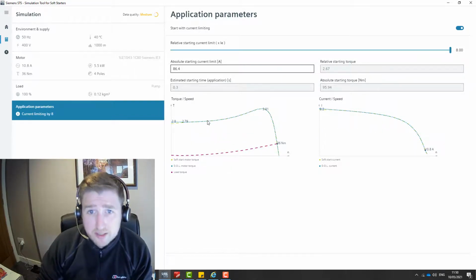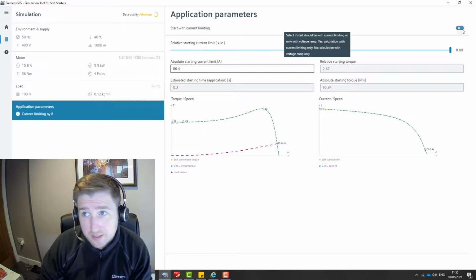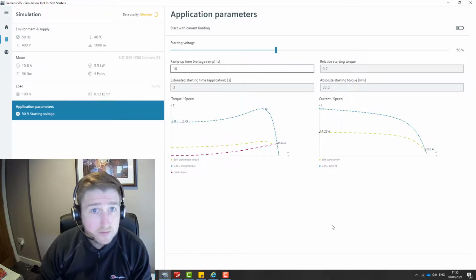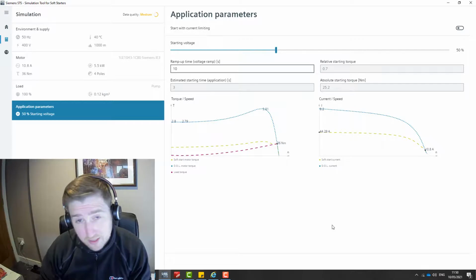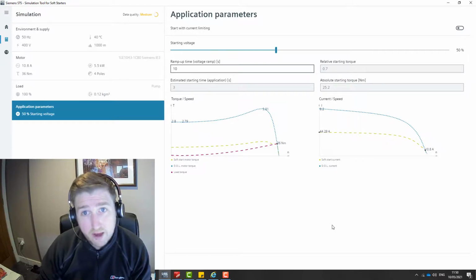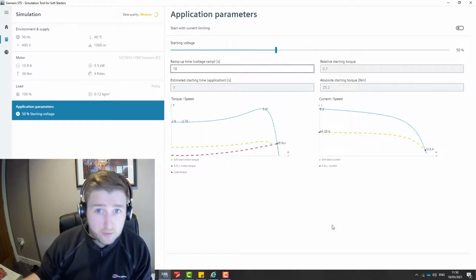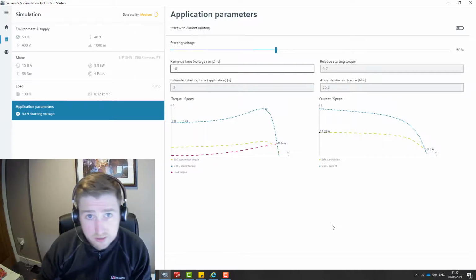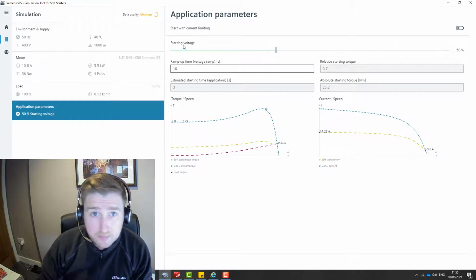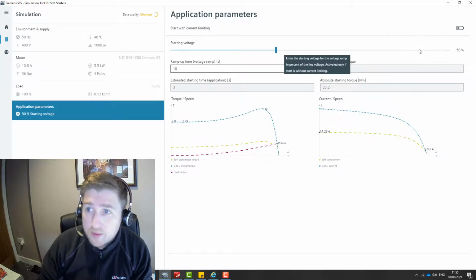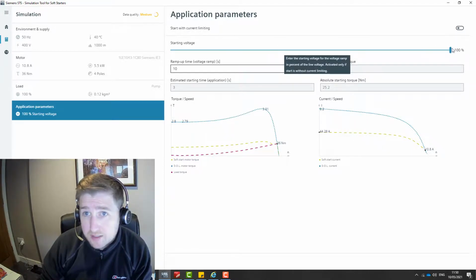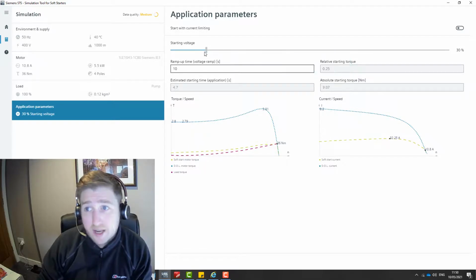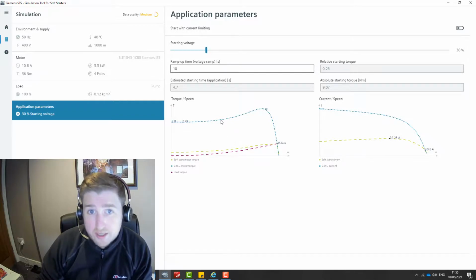And then once that's been done, we can switch the starting current limit function off, and say, okay, let's rely on the starting voltage instead. We don't want to regulate the voltage and have that overriding or being overridden by the starting current. We want to use the starting voltage instead, and then you can parameterize here what the starting voltage could be from the full line voltage. Do we want it at 100%? Do we want it at 25%? It's entirely up to you to gain an understanding of the starting parameters through this simulation tool.